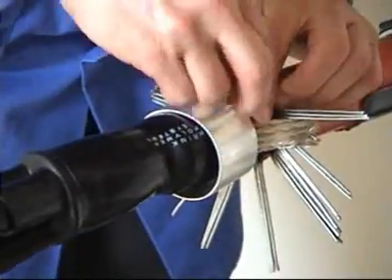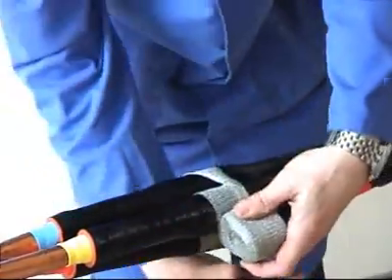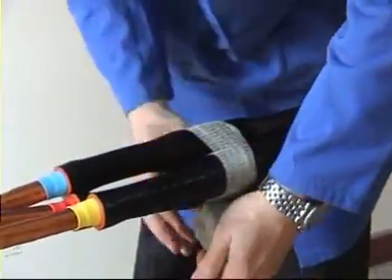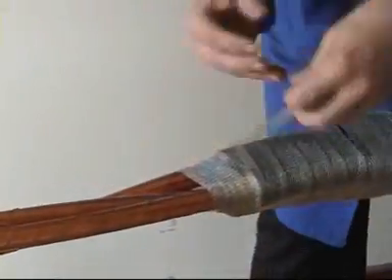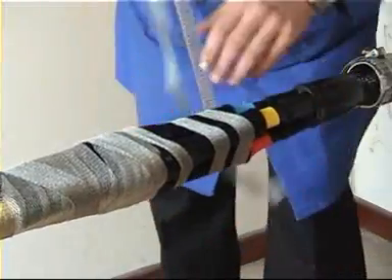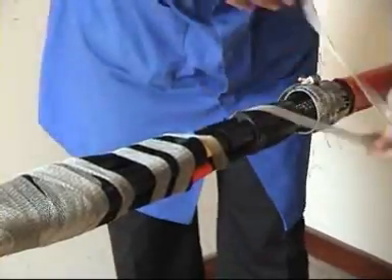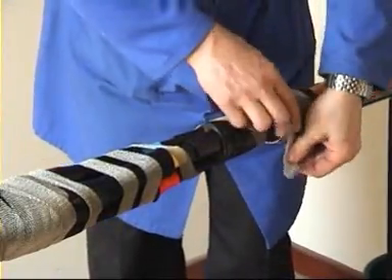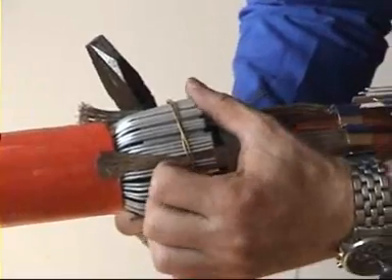The armour support ring is now fitted unless steel tape armour then it's not required. Copper screening bandage should now be applied tightly around the centre of the joint and applied with 50% overlap down onto the copper tapes and then back again and bonded to the remaining cable side at the earth connection point. You can use a binder to temporarily hold the braids in position.